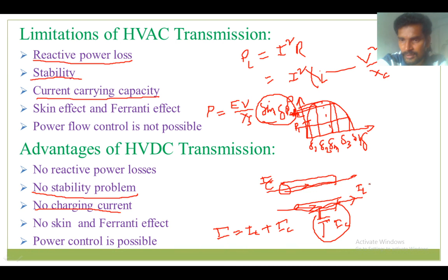Another concern was current carrying capacity. See, for example, this is the conductor. In case of DC, there is no charging effect. So whatever the current taken by the load will be the current carrying capacity. In case of AC, the total current must be the charging current plus the load current. So let this be the load current IL and this be the charging current IC. Then I is equal to IL plus IC. So the current carrying capacity is less in case of HVAC transmission when compared to HVDC transmission. Why? Because it has to carry both the charging current and the load current, but there is no such charging effect in case of DC.